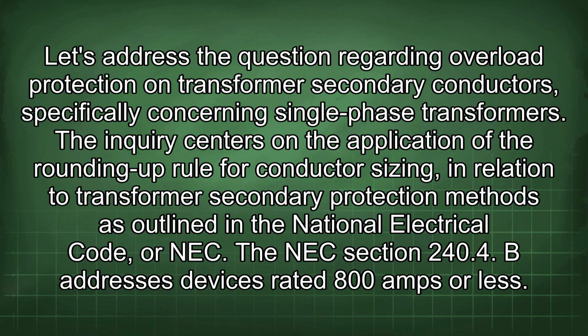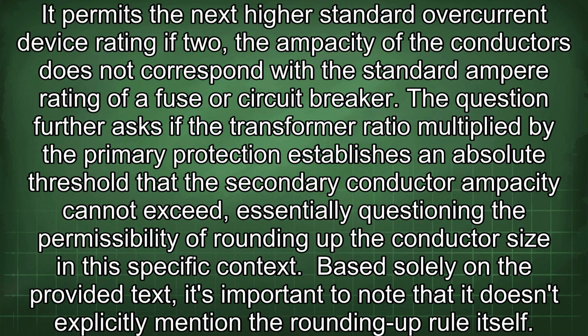The NEC section 240.4(B) addresses devices rated 800 amps or less. It permits the next highest standard overcurrent device rating if the ampacity of the conductors does not correspond with the standard ampere rating of a fuse or circuit breaker.